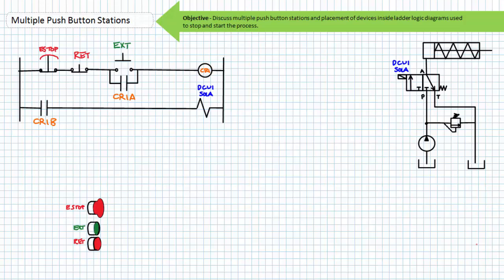This illustrates the logic behind an operator-initiated extension and retraction of a hydraulically extended spring-retracted single-acting cylinder. The ladder logic diagram of this circuit is a repeat of the holding circuit we introduced in the basic ladder logic lecture. Let's review how it functions since an understanding of its function is critical to our current topic. If an operator were to press the extend button, the momentary normally open extend switch would close and via the normally closed e-stop, the normally closed retract, and then the now-closed extend, the coil of control relay one would be energized.